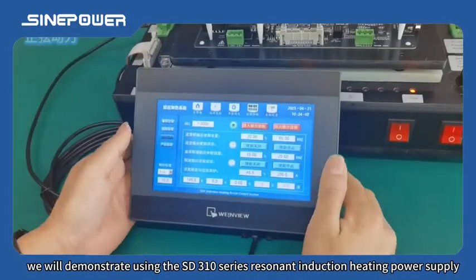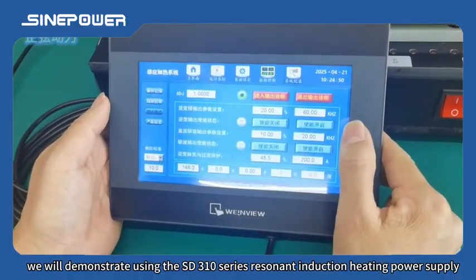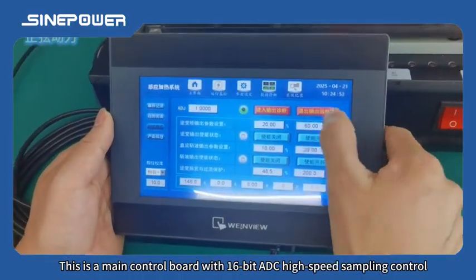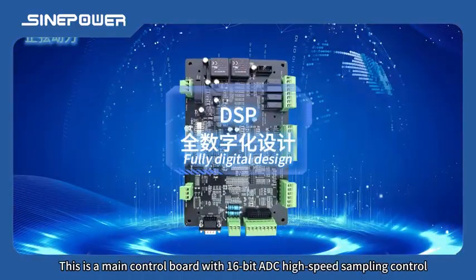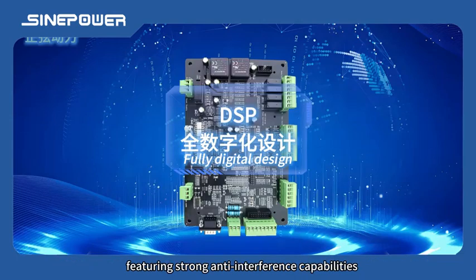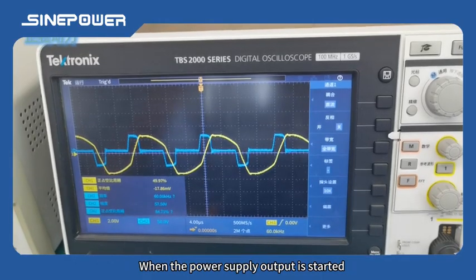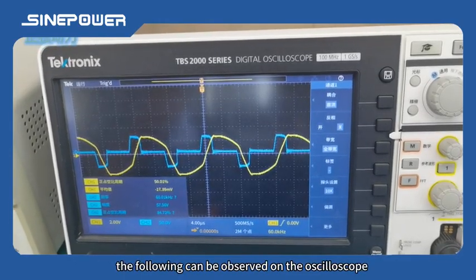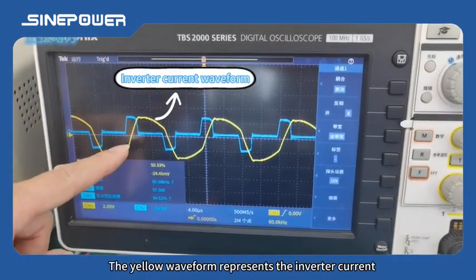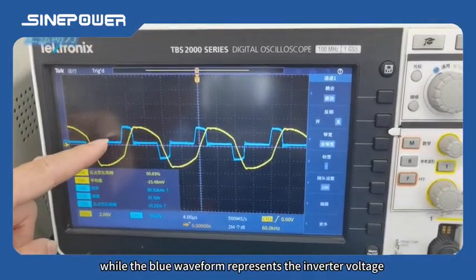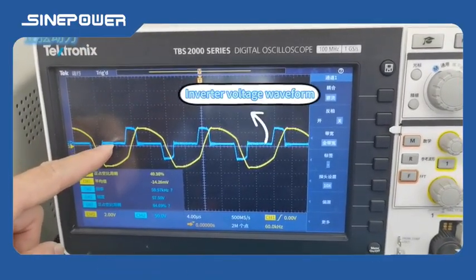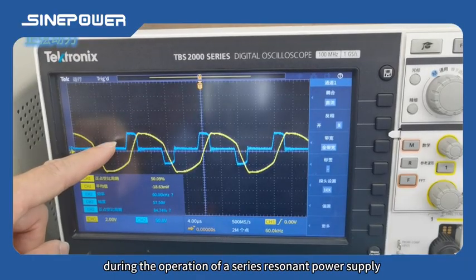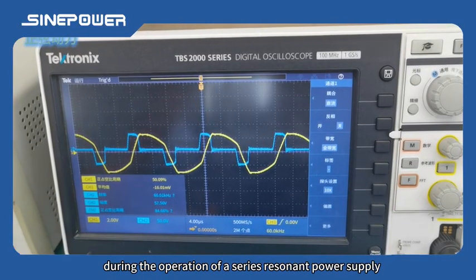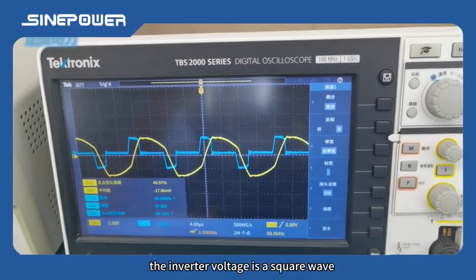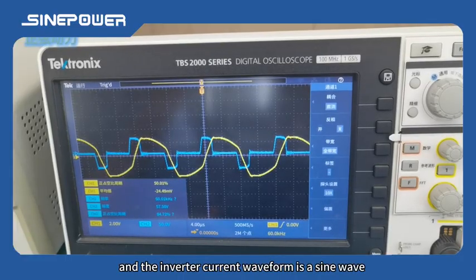Now, we will demonstrate using the SD310 series resonant induction heating power supply. This is a main control board with 16-bit ADC high-speed sampling control, featuring strong anti-interference capabilities. When the power supply output is started, the following can be observed on the oscilloscope. The yellow waveform represents the inverter current, while the blue waveform represents the inverter voltage. It is worth noting that, during the operation of a series resonant power supply, the inverter voltage is a square wave, and the inverter current waveform is a sine wave.